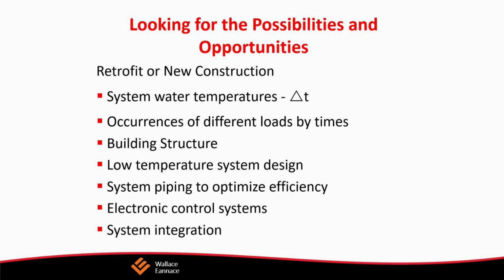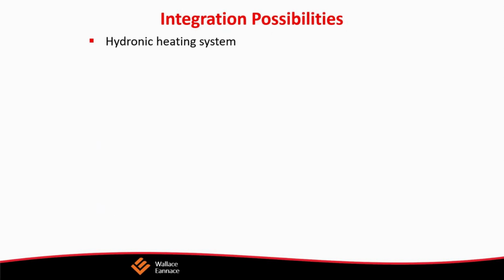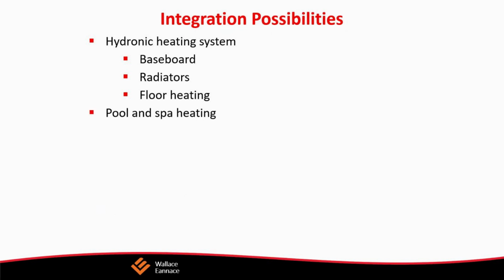We have to consider that there are other possibilities and opportunities. We could be doing a retrofit, or it could be new construction. We want to consider the system water temperatures. What is the delta T, or the change in temperature? We talked before about a 20-degree delta T being critical. In new systems, we may be looking for 30 or 40-degree delta Ts. They may be more applicable, and there are big advantages to that too. You can also have different loads at different times of day. The structure of the building matters: there could be solar gain, there could be particularly cold areas. You have to consider also the actual geometric structure of the building.